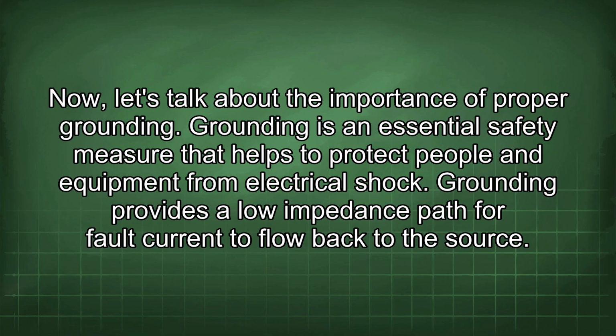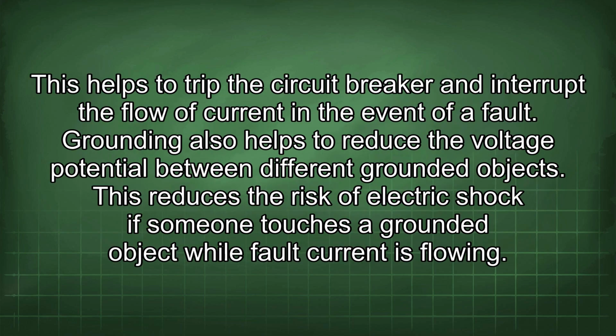Now let's talk about the importance of proper grounding. Grounding is an essential safety measure that helps to protect people and equipment from electrical shock. Grounding provides a low impedance path for fault current to flow back to the source. This helps to trip the circuit breaker and interrupt the flow of current in the event of a fault. Grounding also helps to reduce the voltage potential between different grounded objects. This reduces the risk of electric shock if someone touches a grounded object while fault current is flowing.